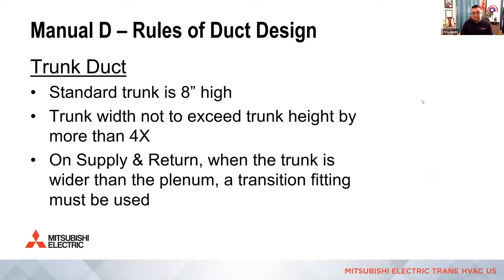Now, standard trunk is typically 8 inches in height. You can go 8 inches by 32 as your maximum width before you have to go to a 10 inch trunk. So it's 4 times the width. That's the aspect ratio. You can't have a crazy aspect ratio of really thin by really wide duct, because you're going to have weird pressure losses and a lot of turbulence.